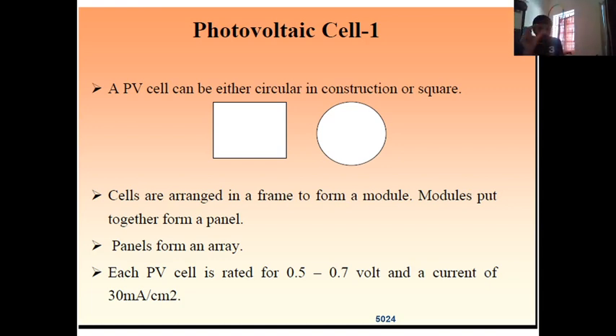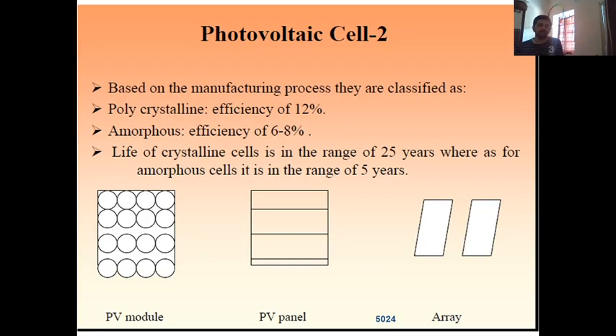Modules put together form a panel. A number of panels connected in parallel can form an array. Each PV cell, a single circular or square geometry PV cell, is rated for 0.5 to 0.7 volt and a current of 30 milliamps per centimeter square. The solar cells are classified based on the manufacturing process as polycrystalline, amorphous, or monocrystalline cells.